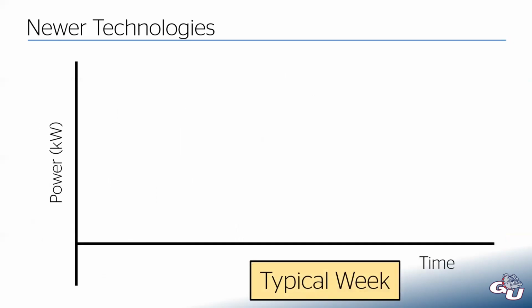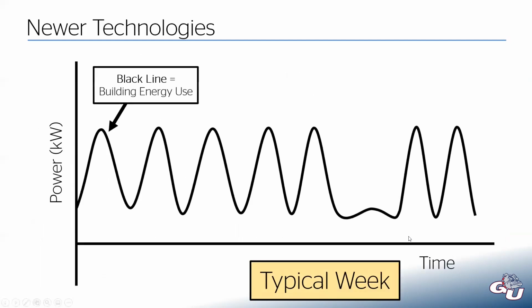So to visualize that, let's say we're looking at our building over a typical week. We have the power draw of our building on the y-axis, time on the x-axis, and let's say this is the general curve of the power use of that building for this given week. So we have these 5 peaks here. That's probably our week, Monday through Friday. And you can see it ramps up in the morning to a hot day when all of our air conditioning systems are running. And then as people leave, it gets cooler outside, and then it just repeats for those 5 days. And then we have this weekend period where we still get maybe a hump, or maybe this is just one day off, say a holiday or something. And then our week starts over again. So that would be our typical power profile.